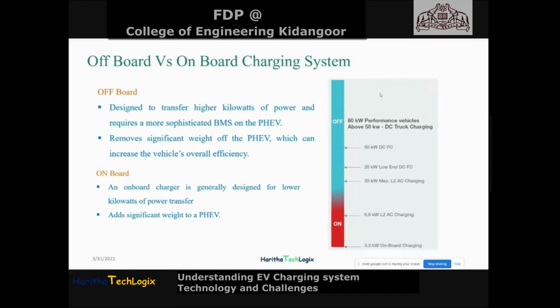The onboard charger is only applicable up to 6.6 kilowatt for a level 2 charger. We call 3.3 kilowatt a level 1 charger, and 6.6 kilowatt means it is a level 2 charger. You can calculate it easily: 6,600 watts divided by 240 volts in India means around 30 ampere current will be supplied continuously. And if it is 3.3 kilowatt, it is a 15 ampere current.